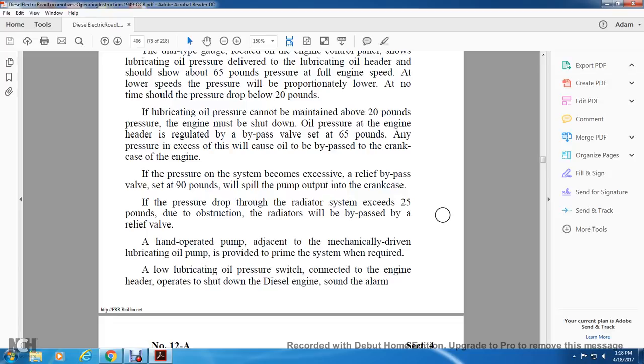If lubricating oil pressure cannot be maintained above 20 pounds, the engine must be shut down. The oil pressure of the engine header is regulated with the bypass valve set at 65 pounds. Any pressure in excess of this will cause the oil to be bypassed into the crankcase of the engine. If the pressure of the system becomes excessive, the relief bypass valve set at 90 pounds will spill the pump output into the crankcase. If the pressure drop of the radiator system exceeds 25 pounds due to an obstruction, the radiator will be bypassed by a relief valve.